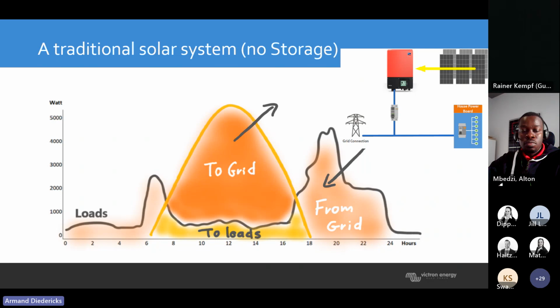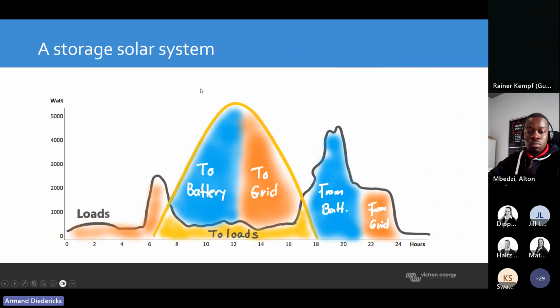So then you can actually install a hybrid inverter, which is the Quattros or the Multiplus units, and connect a PV inverter to the output of the inverter to do peak shaving and provide the load without any issue. So this is how solar storage on ESS works. You've got the battery connected to your inverter side, and from there you've got your solar as well. The primary function of the grid tie system is to provide power to the load first. Then if the load fluctuates and it's not 10,000 watts, it's 2,000 watts, all the excess 8,000 watts can go back to the battery and charge the battery up. And that's exactly how ESS works.